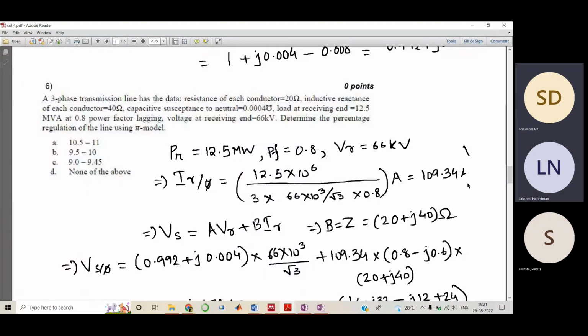But it is mentioned in the question as 12.5 MVA at 0.8 power factor, right? So see, if you multiply the MVA with the power factor, you get the megawatt. That is why you don't need this 0.8 while doing this calculation.